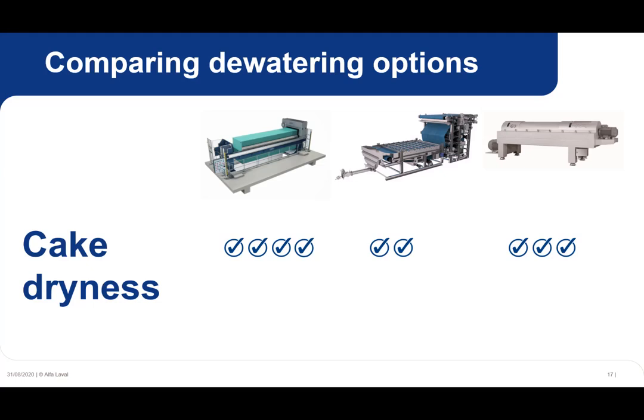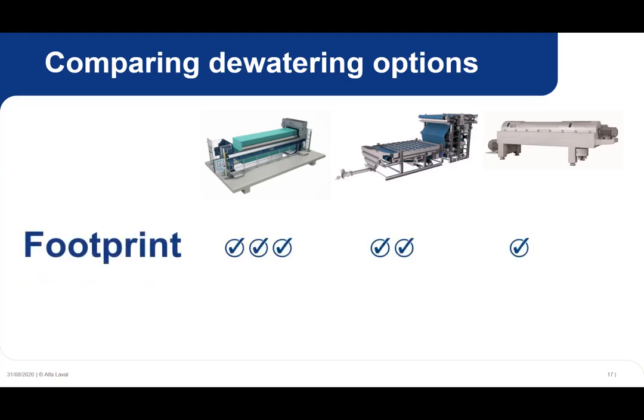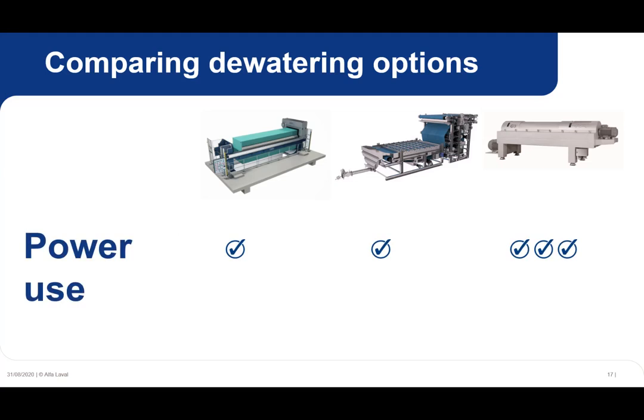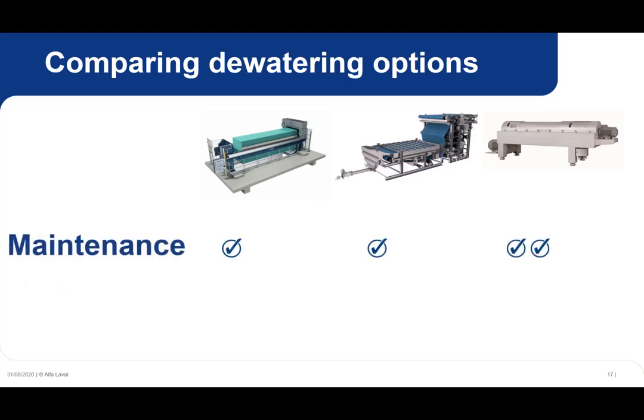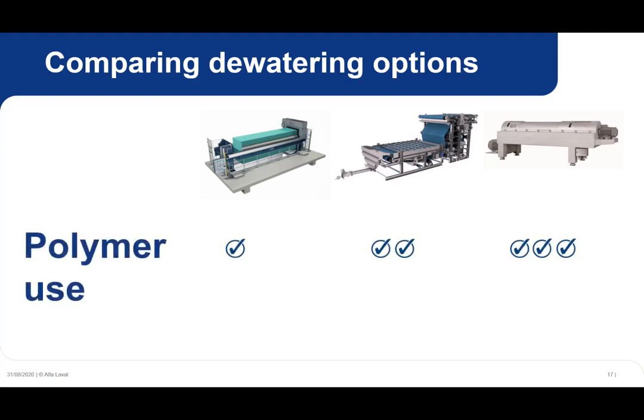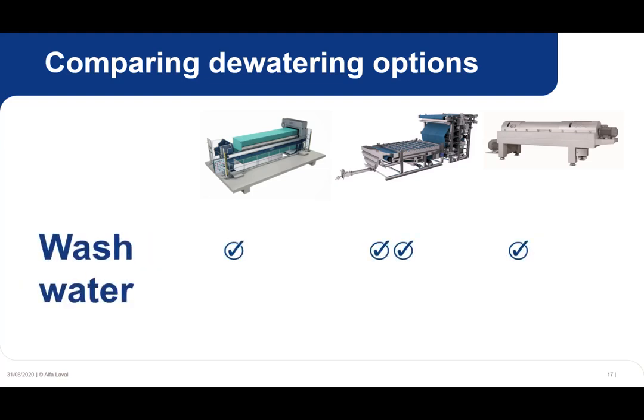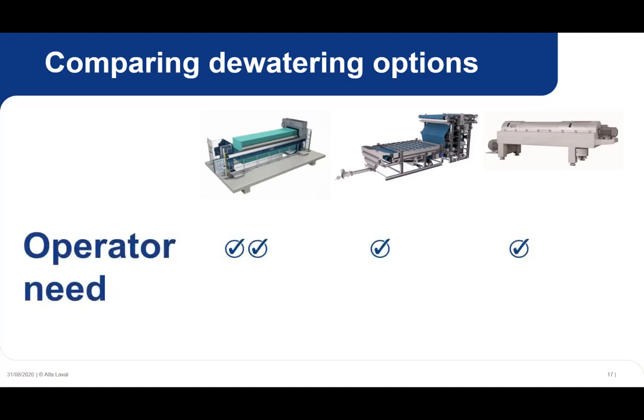As we mentioned before, the decanter centrifuge has the smallest footprint of the three technologies, but also requires more power and may have slightly higher maintenance because of the need to occasionally maintain high-speed bearings. In dewatering, the decanter centrifuge uses slightly more polymer than a belt press, but the belt press does require more wash water. A plate press can sometimes require more operator attention, but there are options that will automate the process, so this may not always be the case.